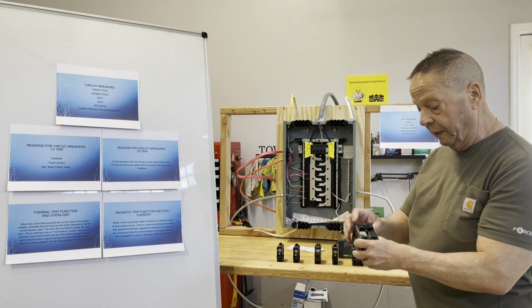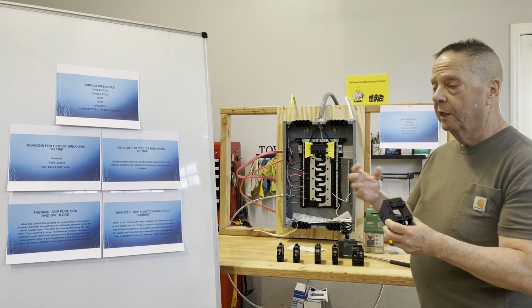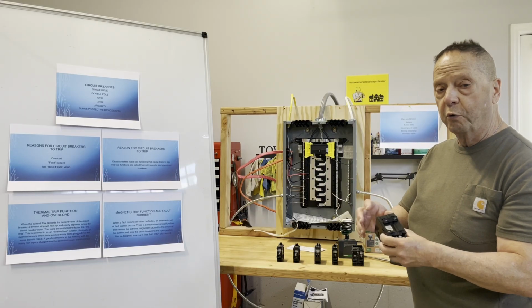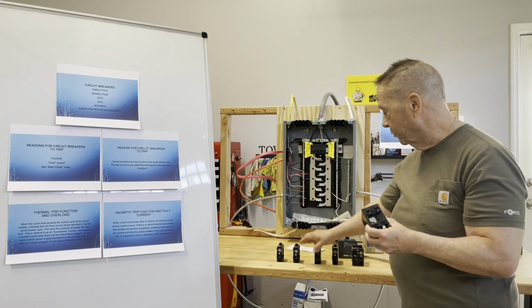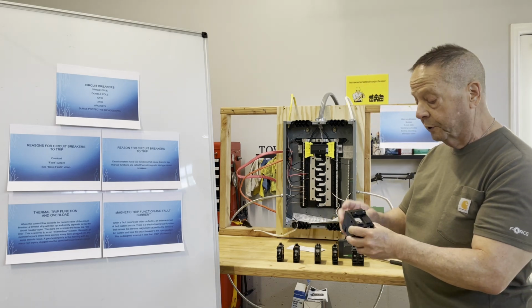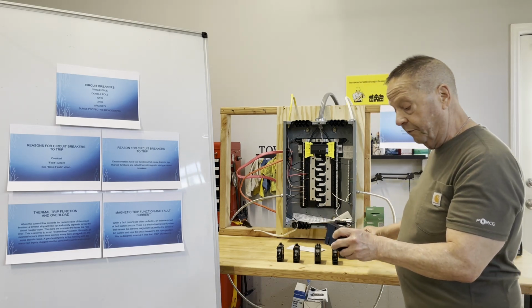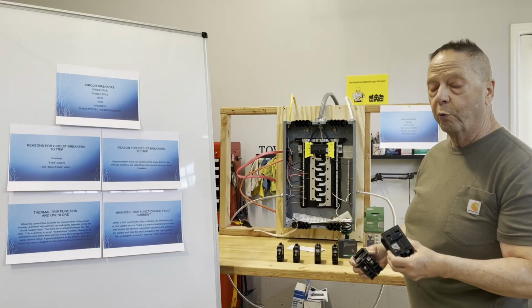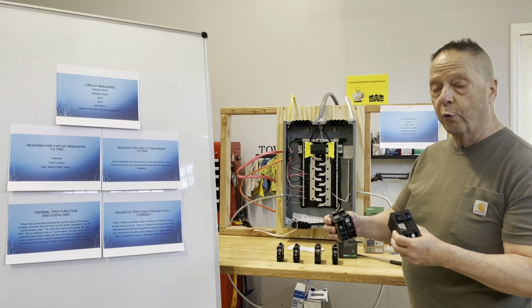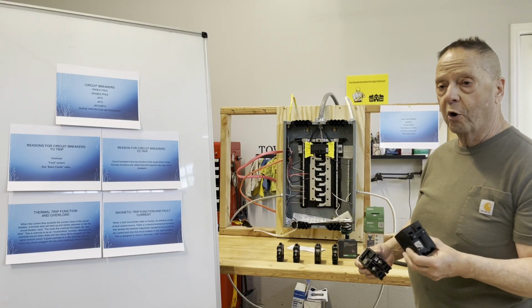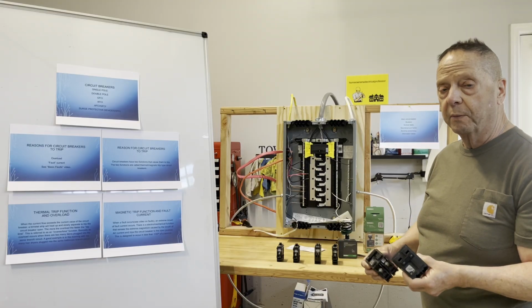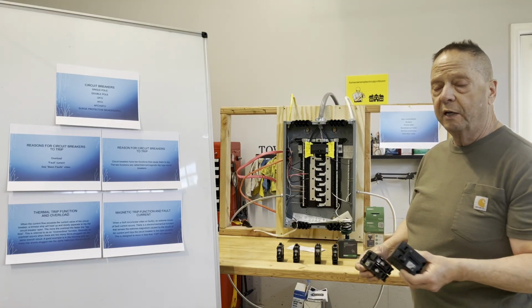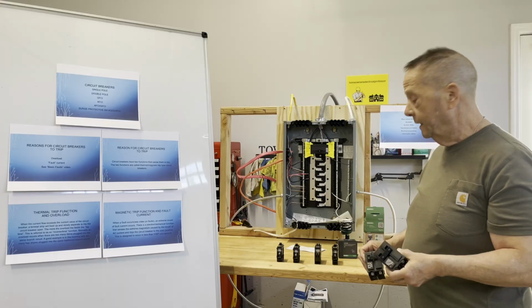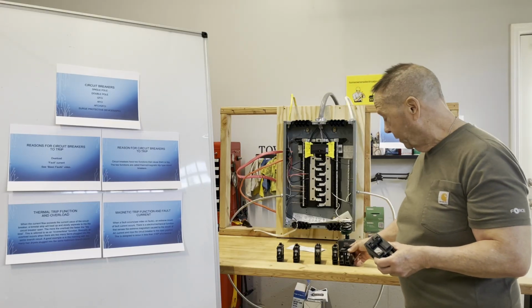These are normally used for fixed appliances. Air conditioning units will be 240 volts, okay? Your single poles are 120 volts. You may have 15s, you may have 20s, you may have 25s, 30s, 40s, 50s. The larger items would probably be some type of electric wall ovens. If you have a gas oven, it's not going to require 240 volts, okay?